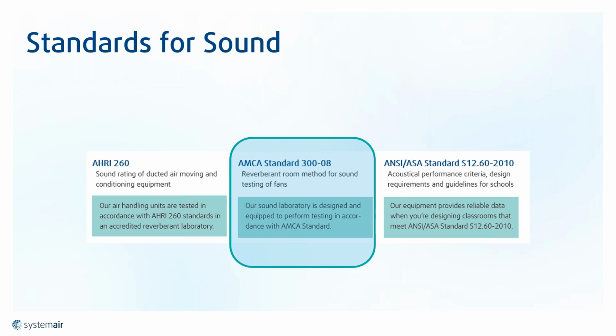On top of that, we took our equipment and measured it in that AMCA lab. It's a reverberant chamber, so it's not one of those sound booths where you place equipment in and the sound is absorbed by those fuzzy cones. It's the worst case scenario, with all the sound bouncing all over the place in that room. So we actually tested our units there, and you know exactly the sound that you're getting.